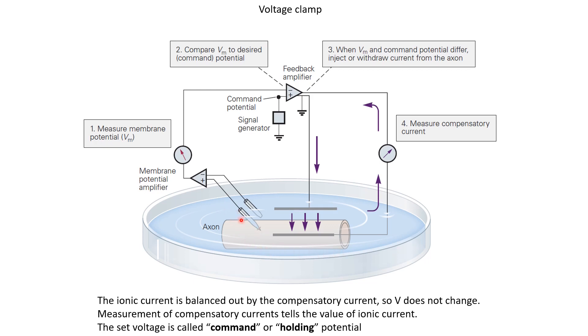We put a recording electrode inside the axon and there is a reference electrode outside. This recording electrode can tell us what is the voltage of the neuron relative to outside, and this difference can be fed to an amplifier to stabilize the recording. For now let us assume there is no amplification happening here, so we are measuring the actual voltage of the neuron. This voltage is fed to the negative terminal of a feedback amplifier, which is very important for voltage clamp and has a very large amplification factor.